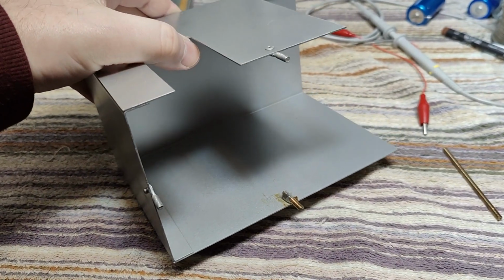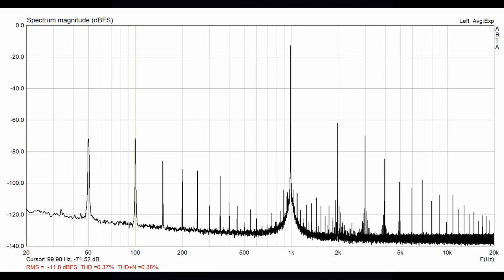Now I think we can assemble all this again. So here is the spectrum of the generator with 4 new capacitors in the high voltage system, and they have double the capacity and half the internal resistance. As we see here, total harmonic distortion is not a lot lower, actually a tiny bit worse. But what we see is all the lower frequency below 500 Hertz is actually much less, and we have less 100 Hertz and 50 Hertz, which is of course better.